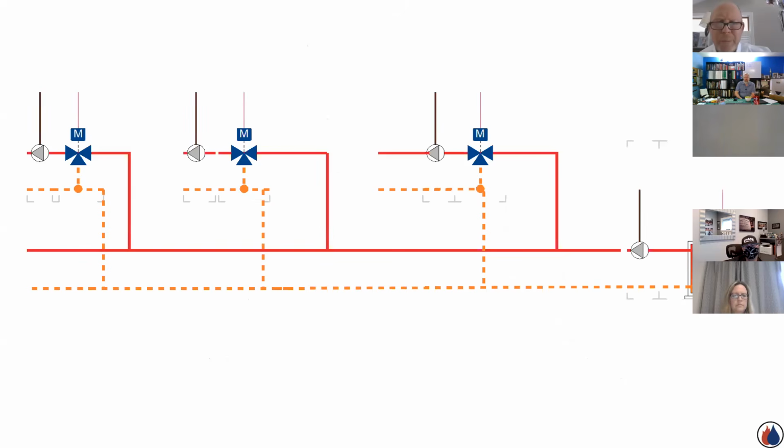Got called out to a building in Brookline, right outside of Boston in Fenway Park. It was 10 large apartment buildings that were converted to 10 very expensive large condominium complexes. Each building received its own energy management system with its own 3-way valve and actuator and reset control and its own distribution pump. And back at the boiler plant, they had a huge, I think it was Cleaver Brooks, boiler and a large 60 horsepower distribution pump responsible for pumping heat through the 10 buildings.